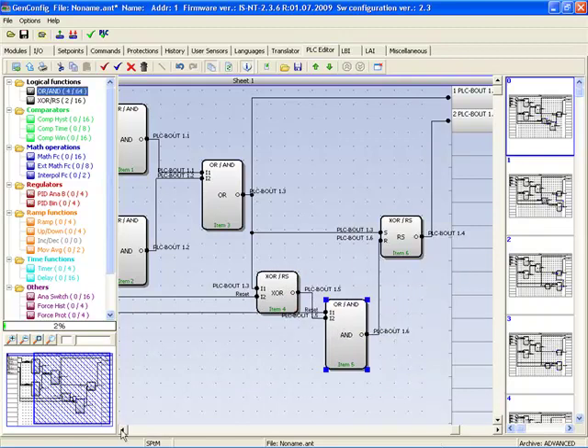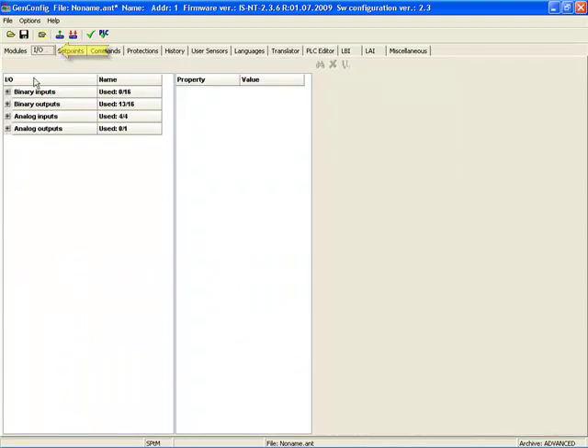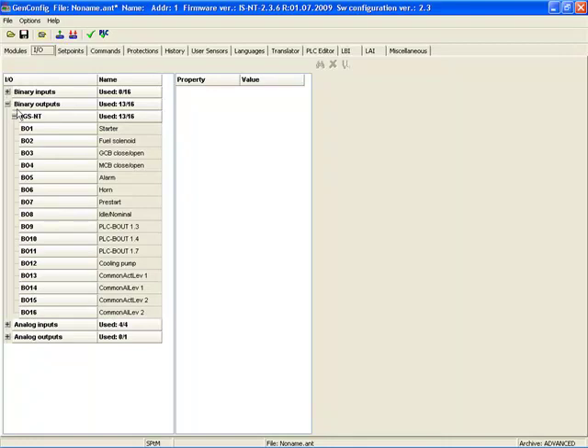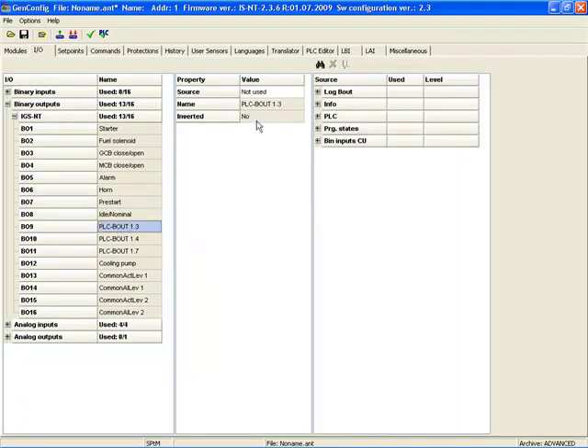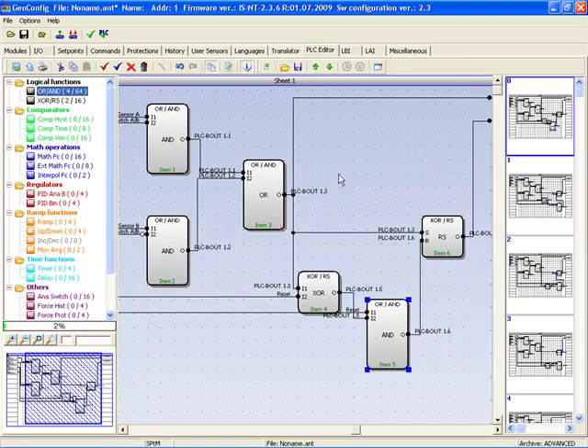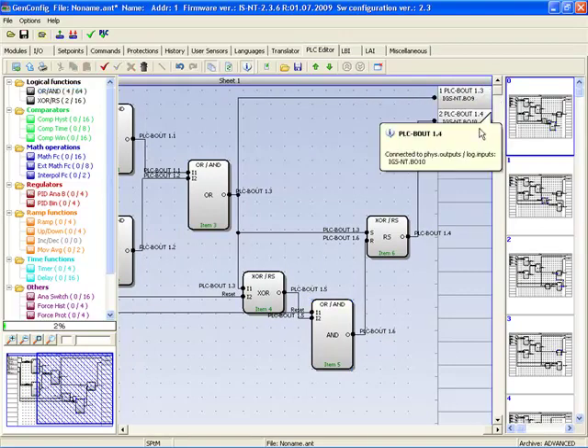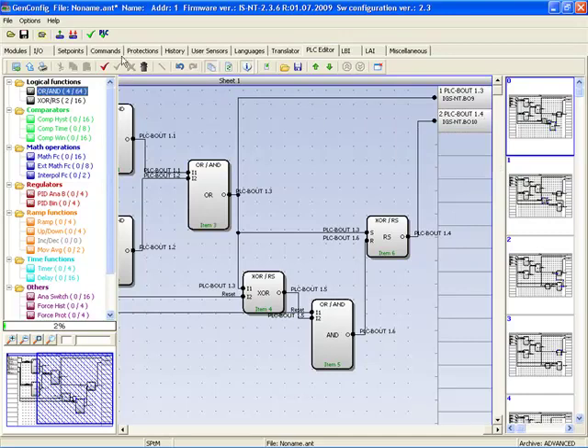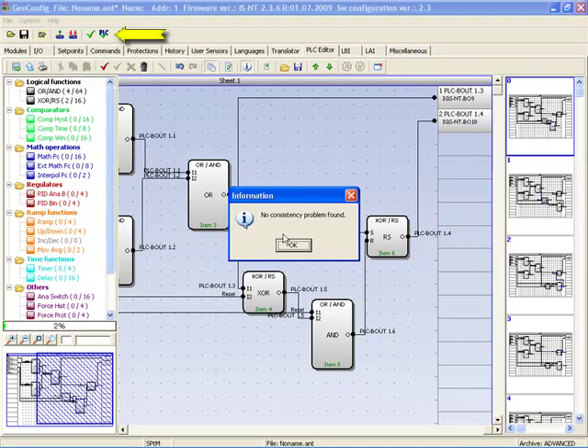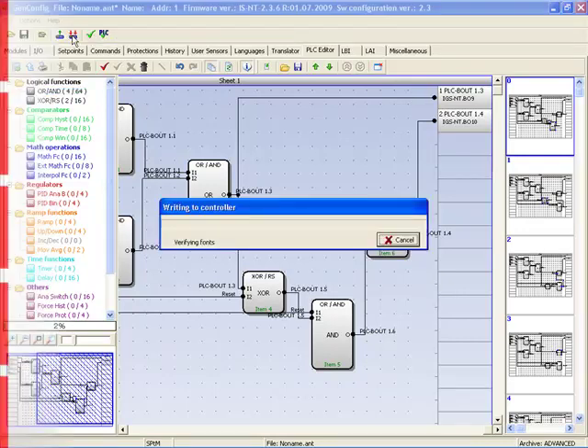Now we have our complete circuit. In the last step we set the binary outputs. We go back to card input and output and set binary output 9 as our present state and binary output 10 as our remember state. Now we come back to the PLC editor and verify that it is defined with binary output 9 and binary output 10. We check the PLC consistency — that's OK, so we can write it to the controller. That's all about PLC logical functions in COMAP controllers.